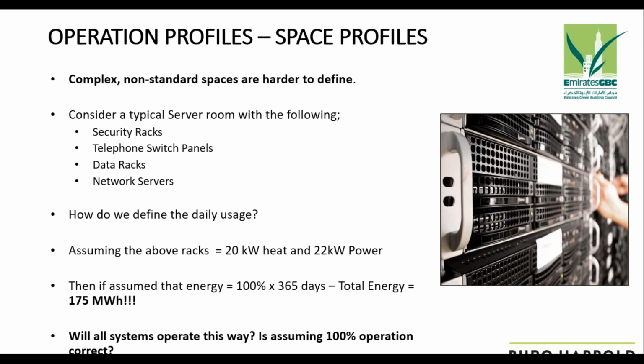But the question is, will all the systems operate this way? Is assuming 100% operation even correct? The answer is that no one knows. We haven't found any data that governs the operation of IDF rooms. Especially when trying to look at savings, to achieve net zero or drive energy efficiency that extra 1%, it's hard to ignore IDF rooms as potential for savings if we could only understand and inform these better.